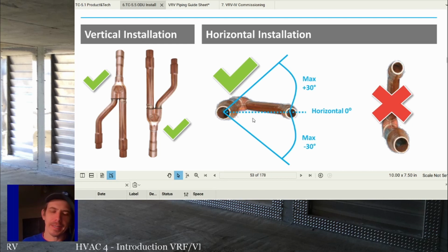And the video that I can't ever find another good one on, maybe I'll have to make one someday. I'll buy one of these Y kits and make a little video. But a good way to think about it is, if water was running in this pipe, would it split evenly as it's running through it? So if water came down here and it hit this joint, it would probably split pretty evenly, right? If water's running up through this pipe and it hit this joint, it would probably split pretty evenly, right? If water's coming through the back of this one, it would probably split pretty evenly. If water's running in here, it's going to want to stay on the bottom and not run through the top.